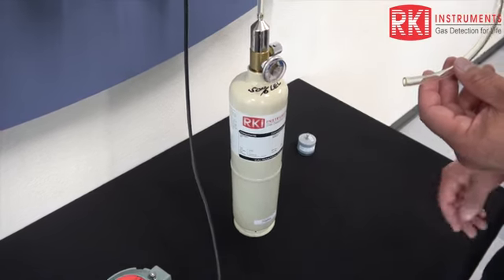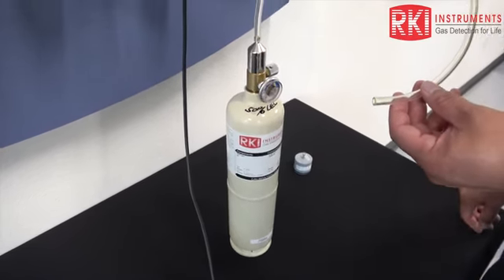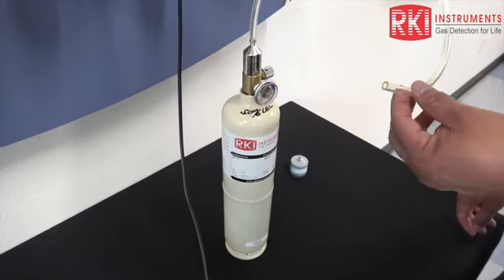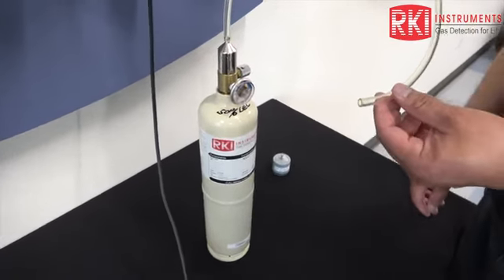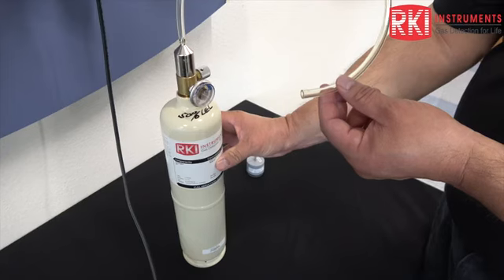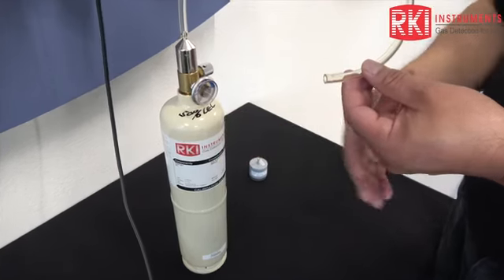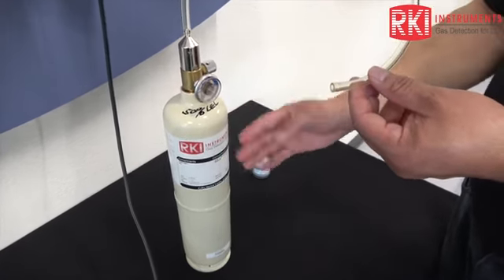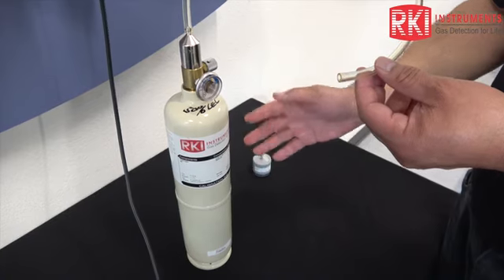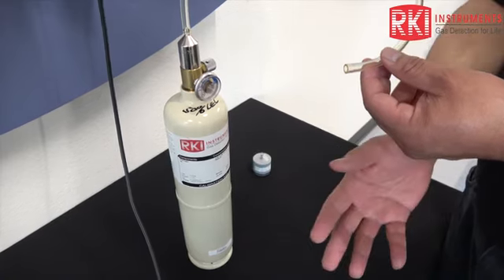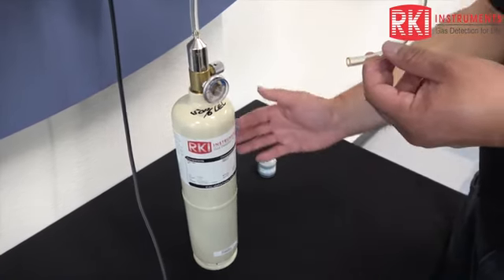But since I'm in the LEL range for this particular detector head, I don't need a humidifier. The reason you need a humidifier is that you have dry gas in the cylinder, there's no moisture, and when you're in a high LEL range, the dryness of the gas doesn't make any difference in the response of the sensor from an ambient air leak versus a cylinder.